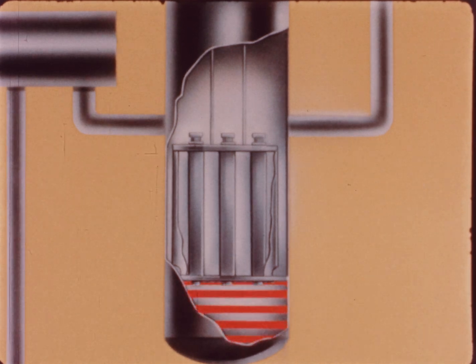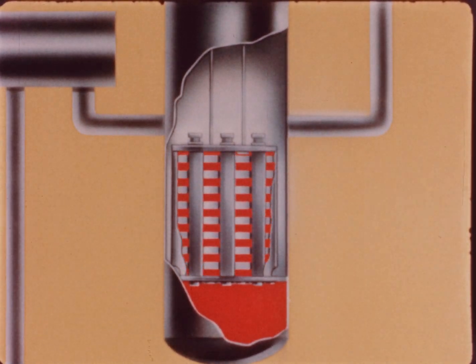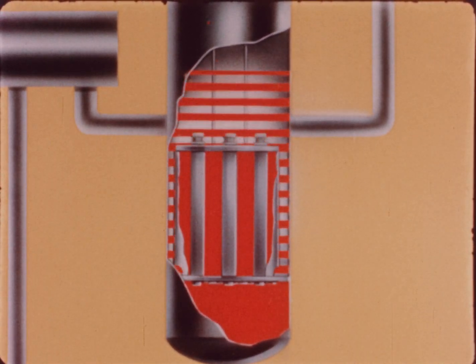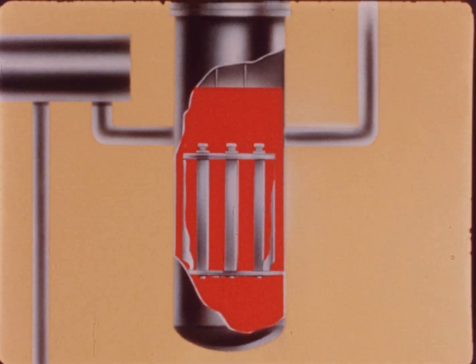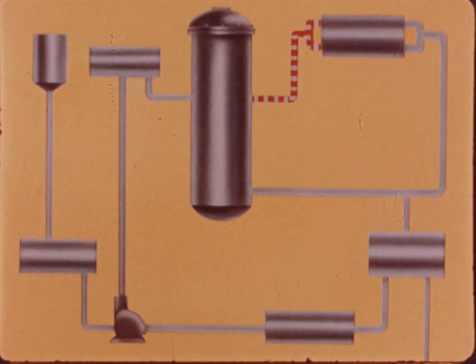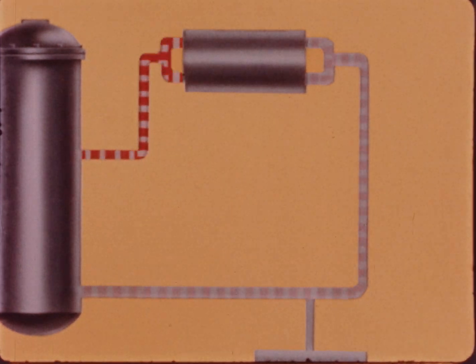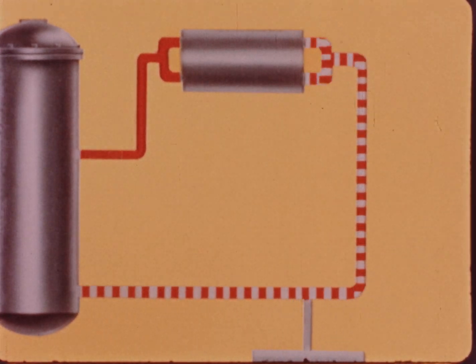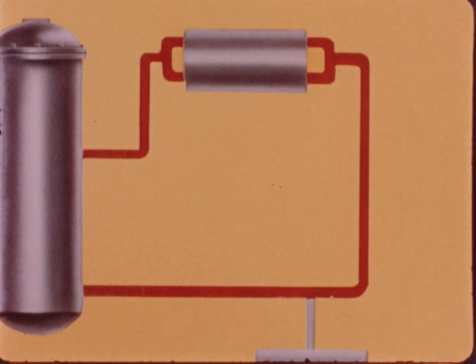The coolant enters the fuel element zone from the bottom of the vessel that houses the core, rises between the fuel plates to remove heat, descends between the fuel elements and control rods, and finally rises between the thermal shield and the vessel wall to a tank located above the core. The organic compound is pumped from the reactor to the heat exchanger, which operates in connection with air blowers, where the heat is dissipated and the coolant returns to the reactor, forming the primary circuit.